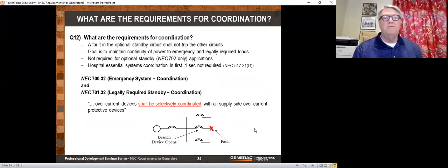This is requirements for coordination. I'm not going to get into this in detail because engineers know all about coordination and other people don't care. That's an overstatement. But in any case, if you have an emergency generator or a legally required generator, it must be coordinated. And that means that, as you see in this bottom rung here, if you get a fault on that circuit breaker in the middle, that circuit breaker should trip before the main circuit breaker feeding the whole panel.